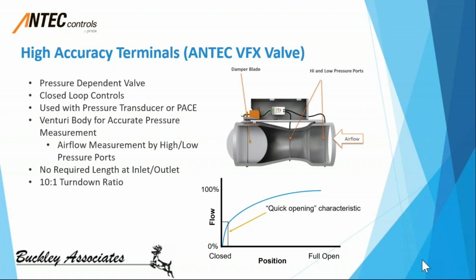A Venturi body generates a pressure drop as air passes through this device. So what we're doing now is measuring the pressure drop with two separate probes, which you can see right here and right here. When we measure that pressure drop, our accuracy of the pressure measurement increases, which again can be calculated directly to an airflow. However, due to its inherent blade damper operation, just like the VAV box, we're still going to see that low end inaccuracy as the blade damper is very close to being fully closed. So this is a better solution than a VAV box, and it remains more economical than a Venturi valve. But if we require a fast responding and accurate airflow management device, we really, really need to look at a true Venturi valve.